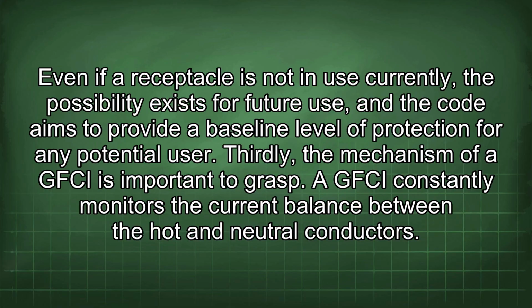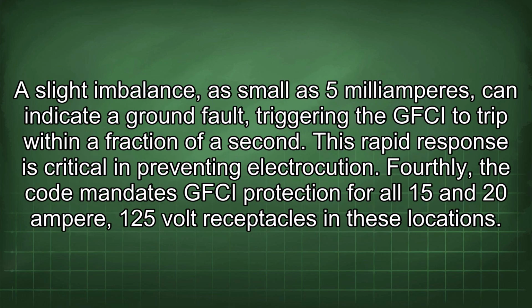Thirdly, the mechanism of a GFCI is important to grasp. A GFCI constantly monitors the current balance between the hot and neutral conductors. A slight imbalance, as small as 5 milliamperes, can indicate a ground fault, triggering the GFCI to trip within a fraction of a second. This rapid response is critical in preventing electrocution.